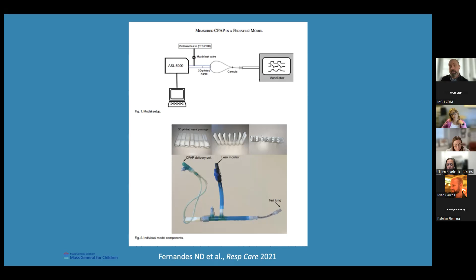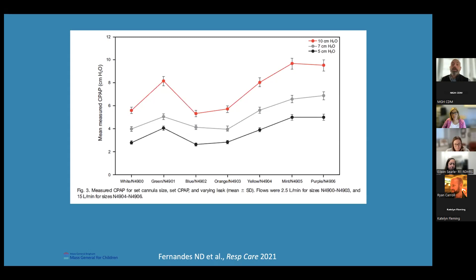We wanted to determine, with 0 to 60% leak, do we see the pressures that we're supposed to be seeing? Does the RAM deliver? And we feel that it does. These are means between the 0, 20, 40, and 60% leak. And the averages tend to be from the orange, yellow, mint or green, and purple sizes on the right-hand side. We deliver the pressures for the most part that are intended, 5, 7, and 10. It's a little bit lower than intended.